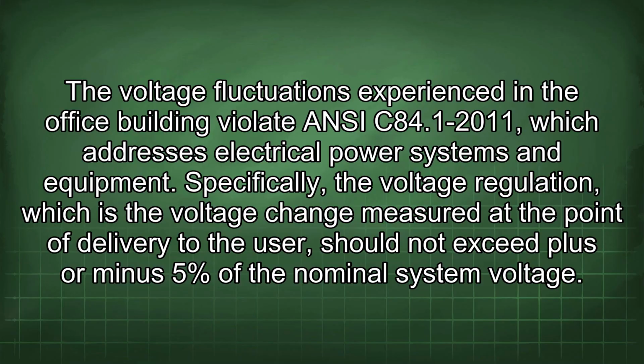The voltage fluctuations experienced in the office building violate ANSI C84.1-2011, which addresses electrical power systems and equipment. Specifically, the voltage regulation, which is the voltage change measured at the point of delivery to the user, should not exceed plus or minus 5% of the nominal system voltage.